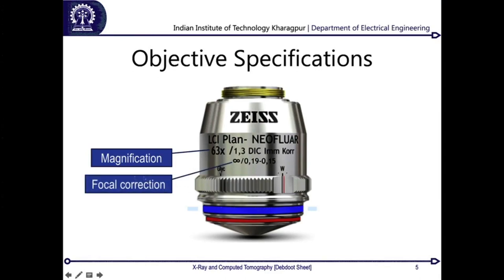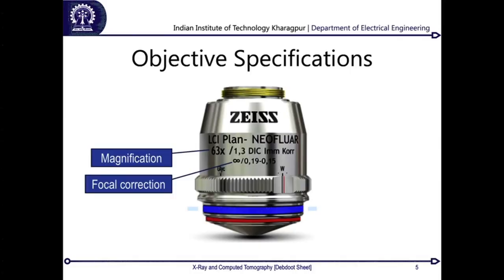The second specification on an objective is its focal correction. Infinity-corrected lenses produce a parallel beam, as if the object is placed at infinity. This is important because if the objective focused at a specific point, the tube lenses would also have to be repositioned every time the objective is moved up or down for focusing — a very complicated optical arrangement. That is why infinity correction is generally preferred, though some lenses do not offer it, which is explicitly stated on the lens.